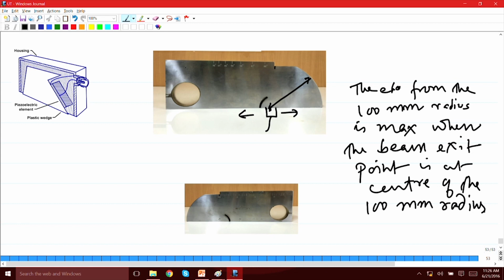this particular method, and if it is not there, then you should mark it like how I said, okay, getting a maximum signal from the 100 mm radius, and then at that particular point you mark the index point on the transducer probe. Okay. So, that is the first thing you do, and then you go on to calibrate the angle and other things. Okay. So, let us see how you calibrate the angle using this particular probe.